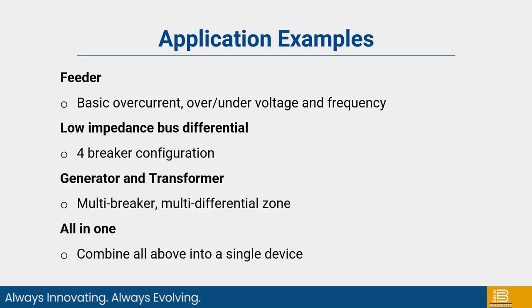So again, we'll go through 4 application examples. A feeder protection with basic overcurrent, over-under voltage, and over-under frequency. We will then go through a low impedance bus differential application with a 4-breaker configuration. We will then go through the generator and transformer multi-breaker, multiple differential zone application. And then last but not least, the all-in-one combining all the above into a single device.